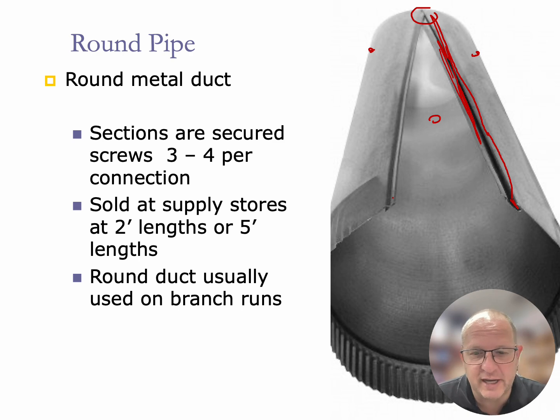So it's sold in 2 foot sections and 5 foot sections from the supply house. Round duct is usually used on branch runs. There is very little restriction for the airflow going through this compared to our flexible duct and the ridges that are on the flexible duct. Just remember that the screw patterns are here on the side and on the other side, and that's going to give rigidity to the piping so it doesn't move. And we want to do that on all the sections of piping that we put on there. Now, if we were to ever take that piping apart and place it back together, we would want to put some new screw holes within that piping on that system itself.